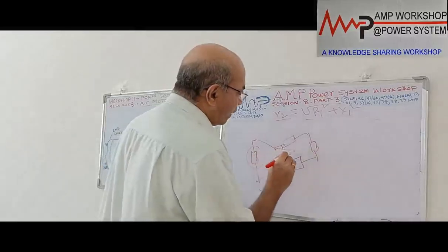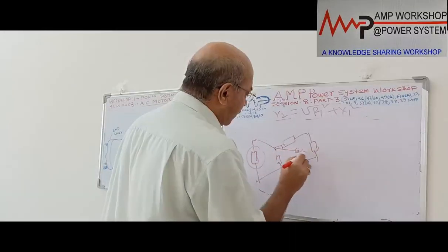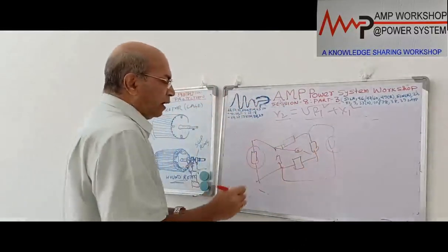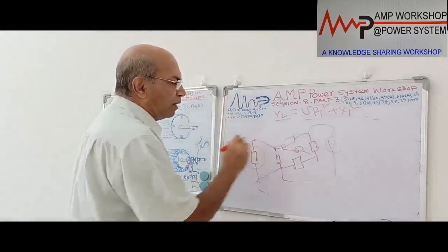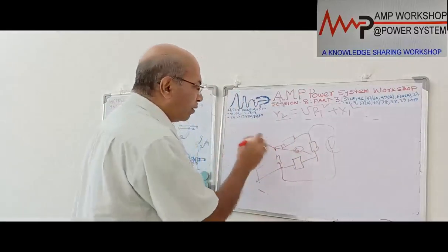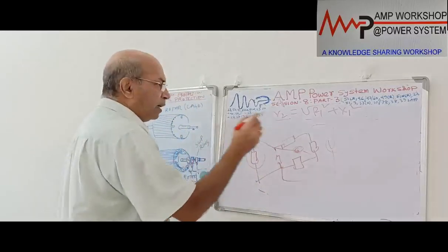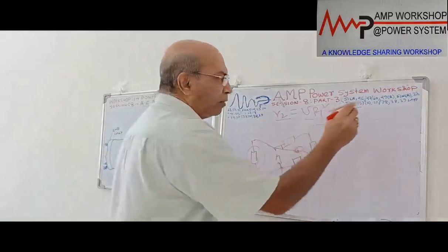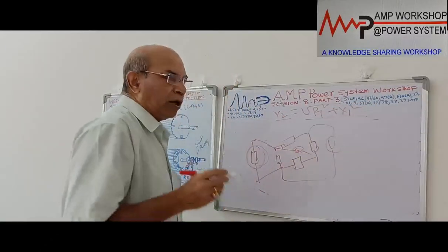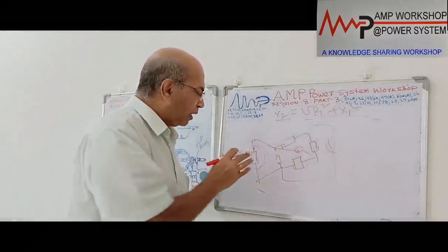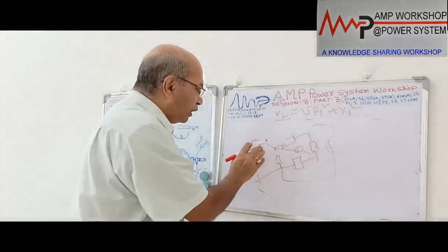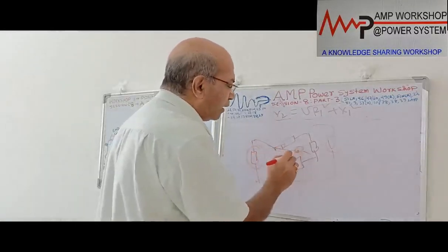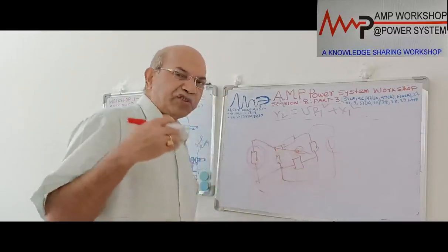Then we connect one ammeter here, and we connect a DC voltage supply over here. Normally, when it is balanced, there is no ammeter reading. But suppose we are tapping on the brush point, and the rotor temperature goes up, then the rotor resistance will also go up. If the rotor resistance goes up, there will be imbalance and there will be current, and we can run a strip chart recorder.